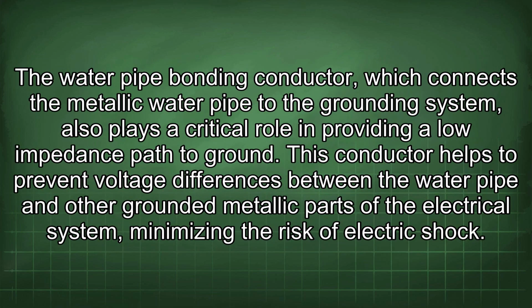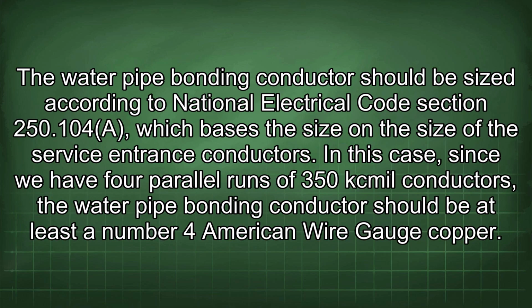The water pipe bonding conductor, which connects the metallic water pipe to the grounding system, also plays a critical role in providing a low impedance path to ground. This conductor helps to prevent voltage differences between the water pipe and other grounded metallic parts of the electrical system, minimizing the risk of electric shock. The water pipe bonding conductor should be sized according to National Electrical Code Section 250.104(A), which bases the size on the size of the service entrance conductors. In this case, since we have 4 parallel runs of 350 kcmil conductors, the water pipe bonding conductor should be at least a number 4 American wire gauge copper.